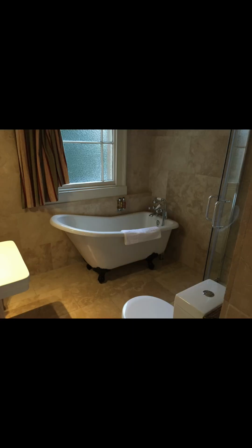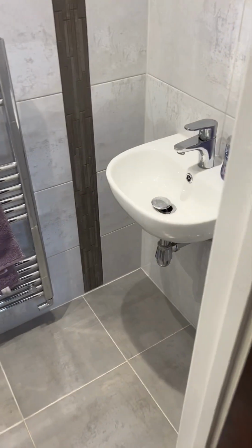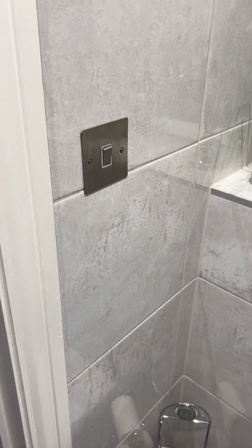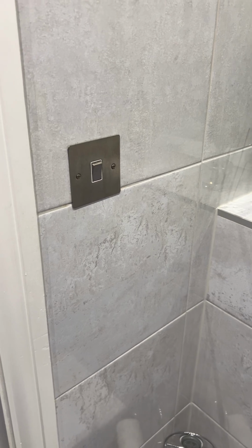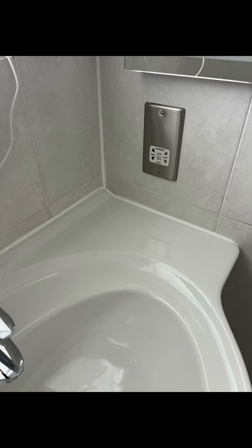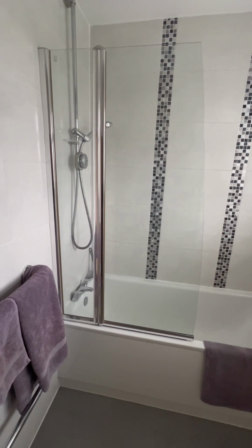We'll start with your basic downstairs toilets and cloakrooms, things like that. Basically, there's not many rules in here, so yeah, you can have switches in here, fans, accessories, it doesn't really matter too much. Because there's nothing with a body of water in it, there's not so many rules around that. Same for sinks in general in the kitchen. As long as they're generally 30 centimetres away, it's normally not a problem. Shaver points can even go a bit closer as well.